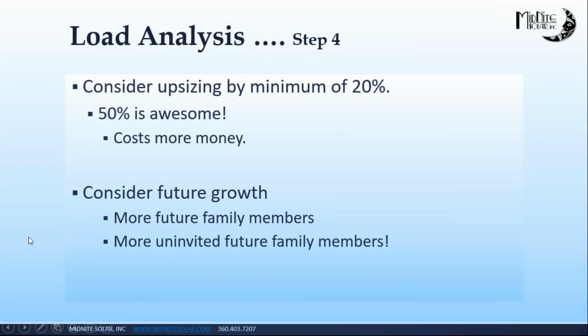When you get to your load analysis, with 4,500 watt hours, I'd recommend kicking it up by 20%. That covers other factors like reactive power and inverter inefficiency. Some inverters run at 94% efficient, some of the cheaper modified sine wave ones might be 85% if you're not running them at full power. There are other loss factors too, so adding at least 20% will serve you well.